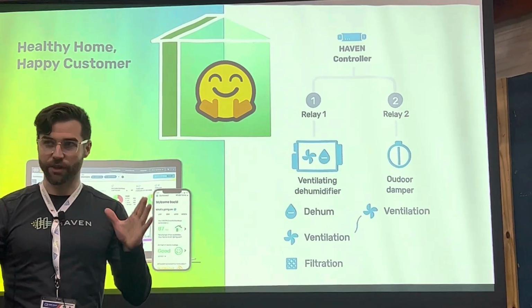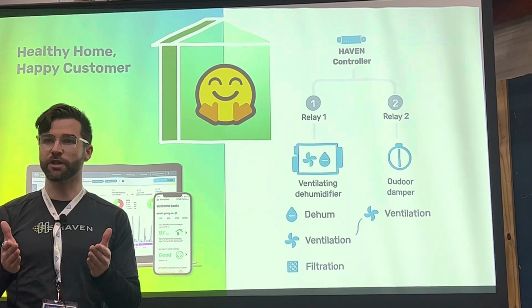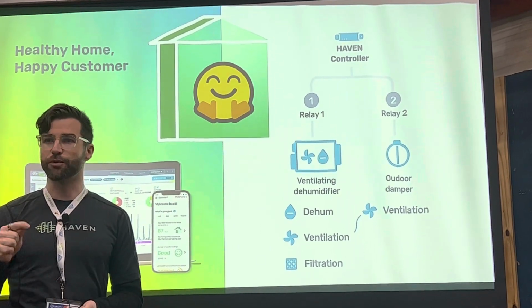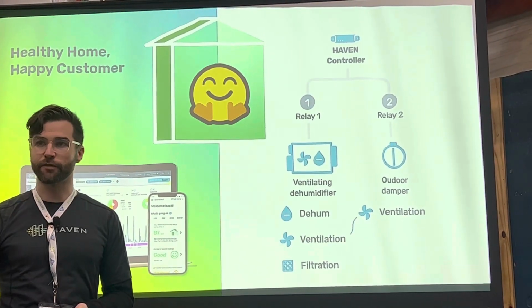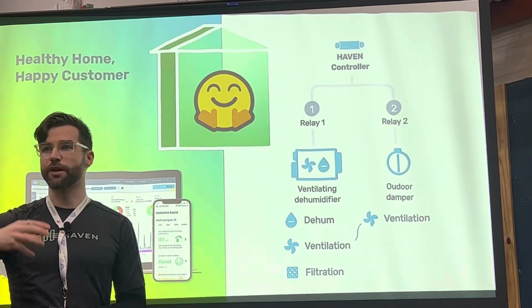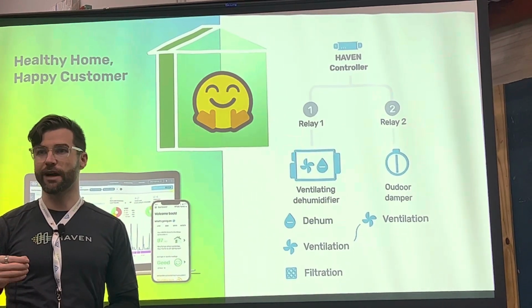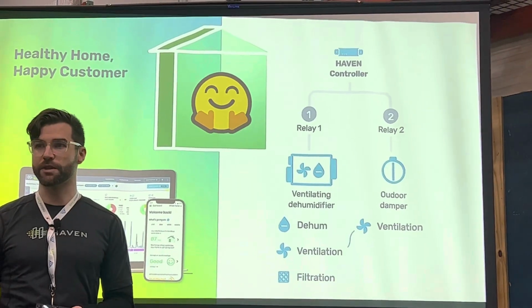the equipment now. Not to say that it isn't important to step through those building science steps, but a lot of the sins of an oversized piece of equipment can be solved because a reheat dehumidifier will heat up the air, will therefore change the sensible temperature of the air for that thermostat, and will therefore run the air conditioner longer. Now you're going to get longer run times. So adding a reheat dehumidifier gives you longer run times, even with an oversized piece of equipment.